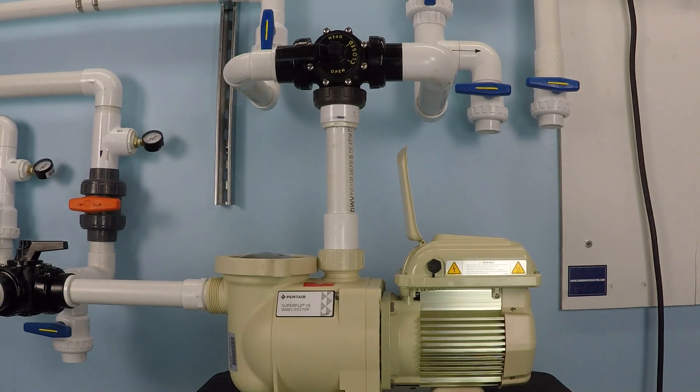In this video, we have a Pentair SuperFlo variable speed pump that is installed and running on inch and a half sized plumbing. Currently, this pump is running at half maximum RPM value. 3,450 RPM is the maximum speed for this electric motor. I've got it running at half of that value right now so that we can examine what the flow rate is and what the electrical consumption is with this pump running under these conditions.